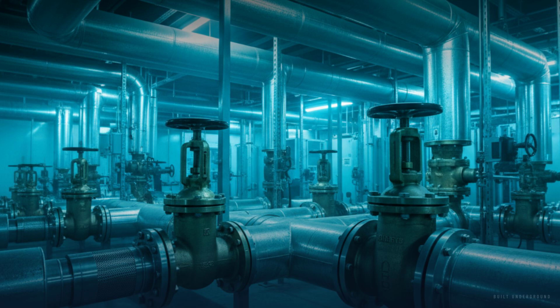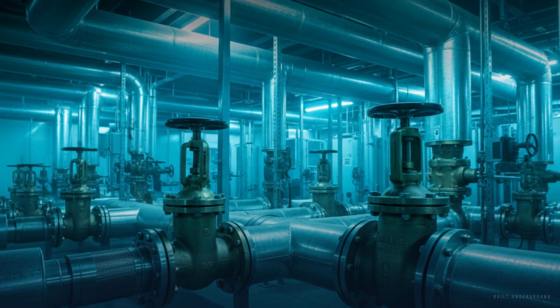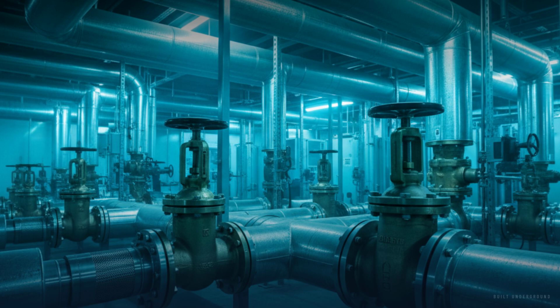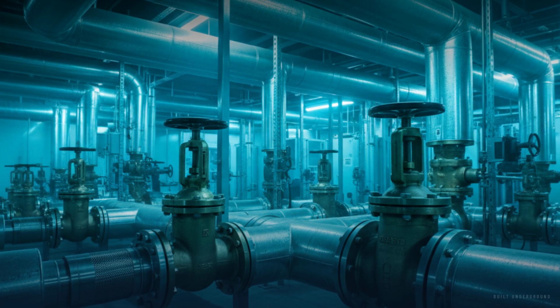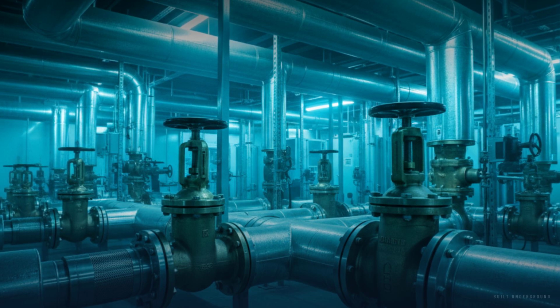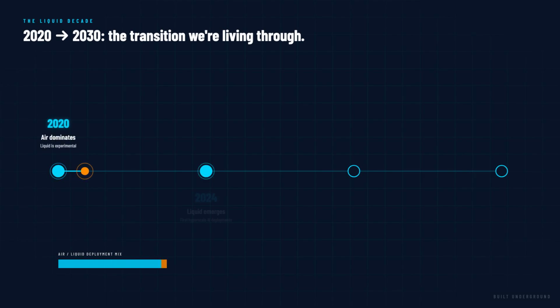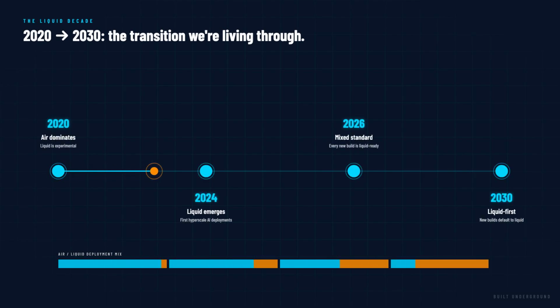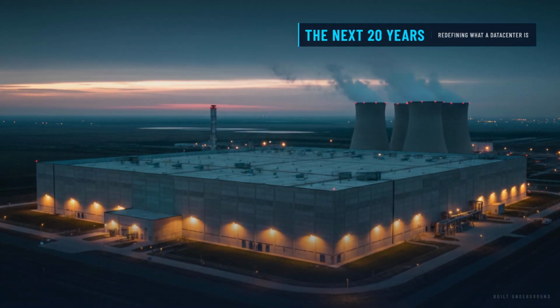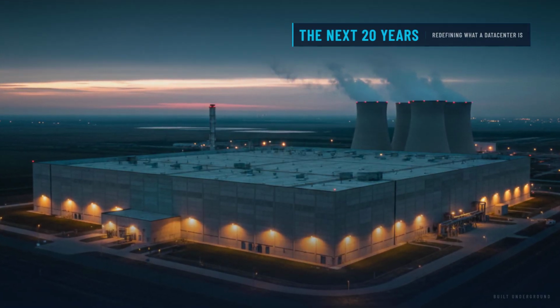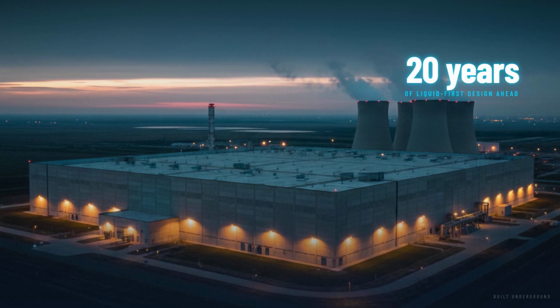For AI training, inference at scale, and any workload exceeding 20 to 30 kilowatts per rack, liquid cooling is no longer optional. It is the only path. The war is not really liquid versus air. The war is between the old assumption that a data center is a room you blow cold air through, and the new reality that a data center is a thermal management system that happens to have servers in it. That shift is going to redefine how these buildings are designed and built for the next 2 decades, and it is happening right now.